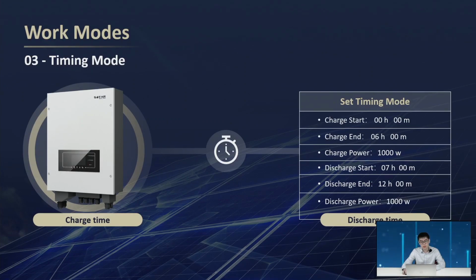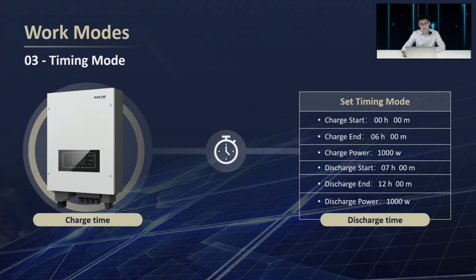Number 3, timing mode. Normally we use this mode to test the charge and discharge function. So we can directly set the charge to start from 0 AM to 6 AM at charge power 1 kilowatt. And for the discharge, here we set it from 7 AM to 12 AM at the discharge power 1 kilowatt. But please mind that outside the time period you set, the inverter will be on standby. So normally we suggest customers use auto mode or time of use mode. This timing mode is almost for testing.